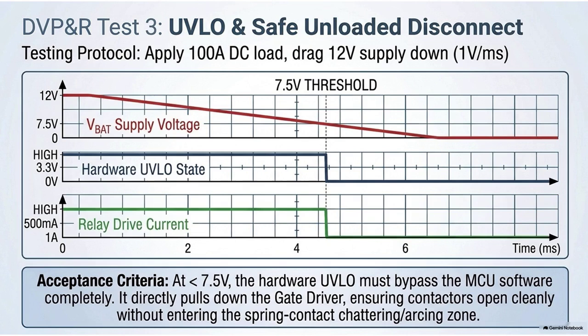So you have a massive amount of lethal energy flowing through the system. Exactly. And while that 100-amp DC load is flowing, they intentionally choke out the 12-volt coil supply. They ramp the voltage down slowly, pulling it down at a rate of 1 volt per millisecond, intentionally trying to force the electromagnet to weaken and allow the spring to bounce the contacts. They're aggressively trying to induce the jitter arc zone while under heavy load. Yes. They're testing the exact millisecond the hardware comparator trips. The instant the supply crosses the critical 7.5-volt UVLO threshold, the analog hardware must forcibly sever the coil drive current, ignoring any input from the microcontroller.